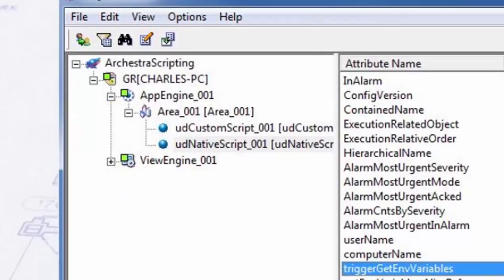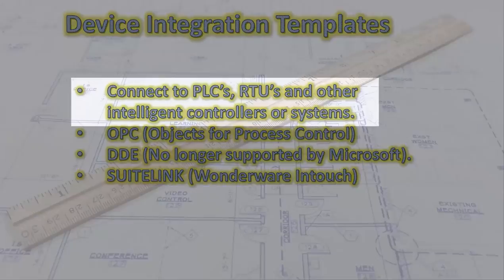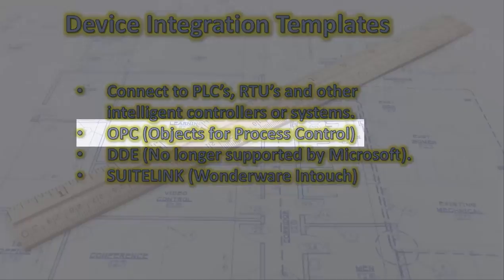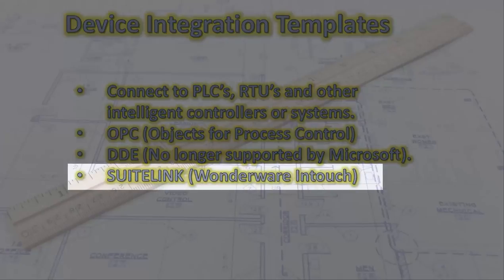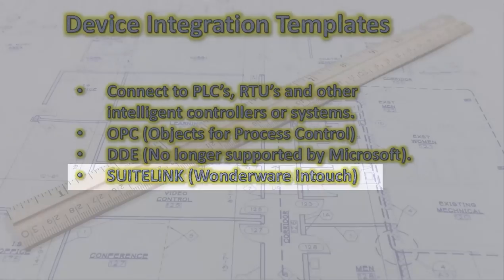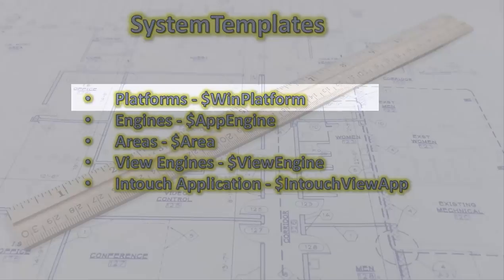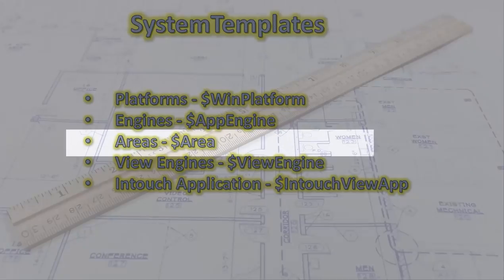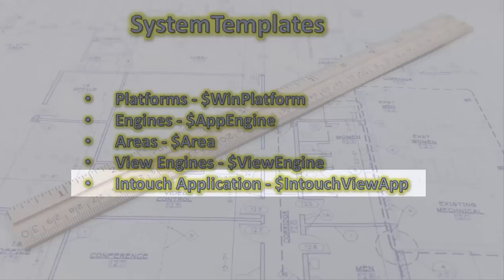Device integration templates allow you to connect to PLCs, RTUs, and other intelligent controllers and systems. You have OPC — Object Linking and Embedding for Process Control — DDE, though no longer supported by Microsoft, and SuiteLink, which is the native communication protocol for Wonderware. System templates: platform objects are generated from the WinPlatform template, engines from the AppEngine template, areas from the area template, view engines from the view engine template, and InTouch applications from the InTouch View App template.